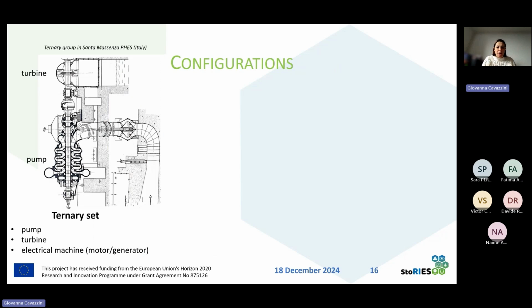Looking in more detail at the hydraulic machine inside the pump hydropower plant, there are two different configurations, and this affects the characteristics of the power plant. One option is the ternary set, composed of a pump connected through a clutch to a turbine on the same shaft. Both machines are connected to a single electrical machine that can operate as motor or generator depending on the needs.